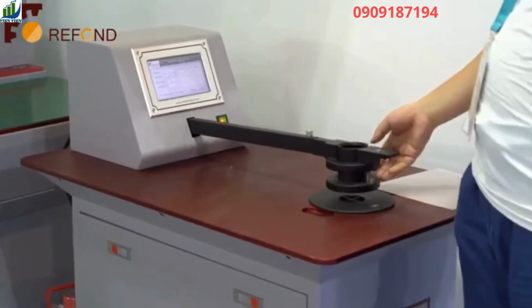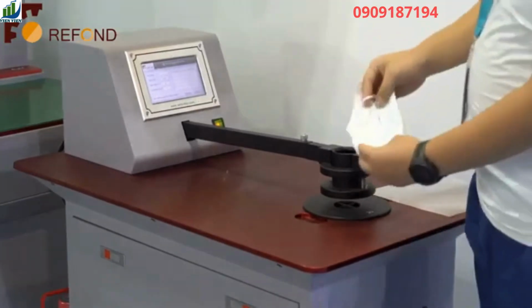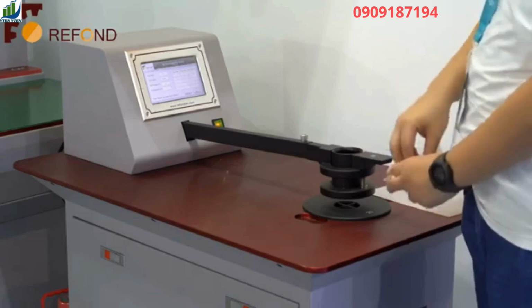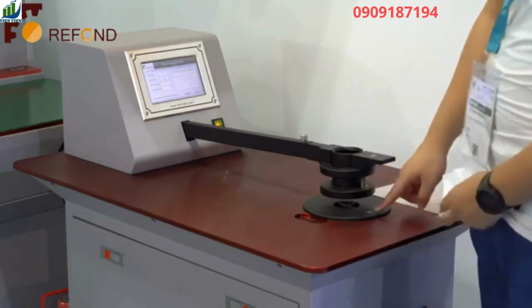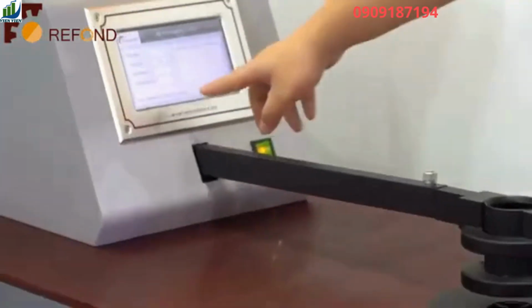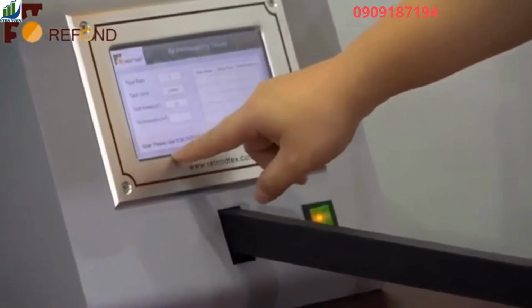The fixed flow rate test is a measurement of the breathability of a face mask. It's also called the flow resistance of the face mask, so it measures how difficult it is for the air to move through the face mask. For this test, you need to use the 5 centimeter squared test head. We have a reminder up here on the touch screen, for reminding the user.